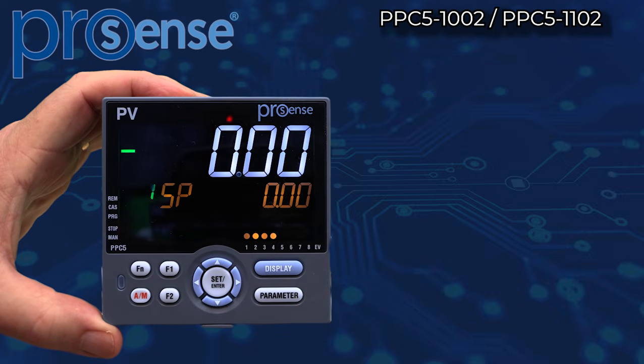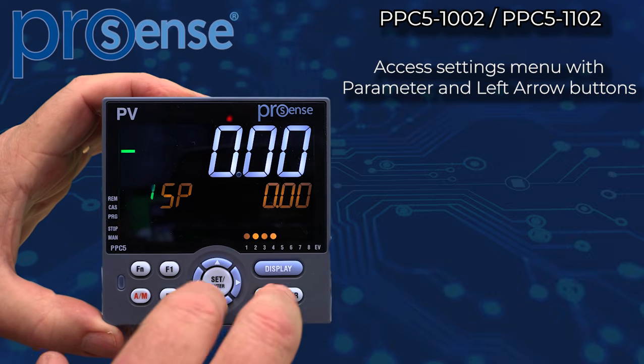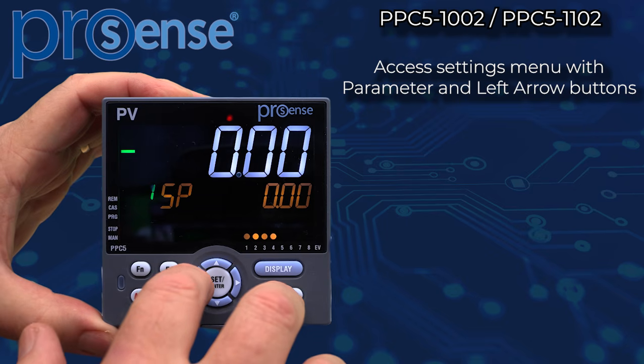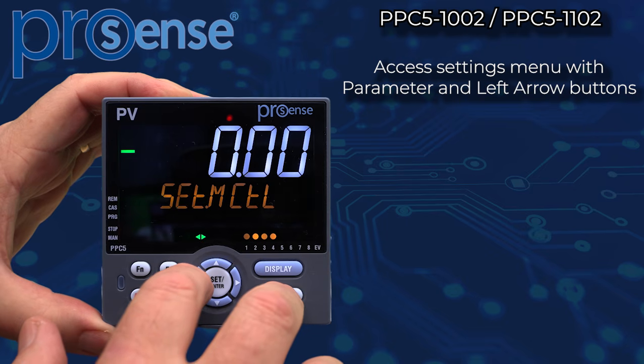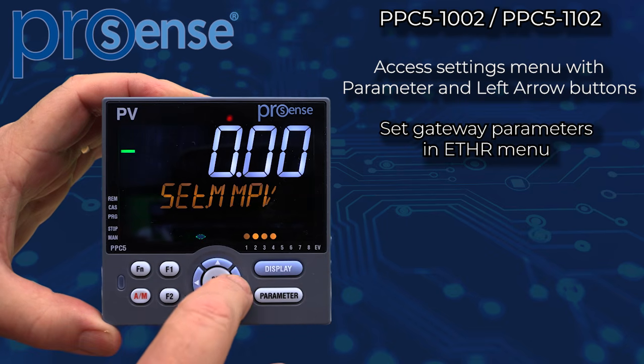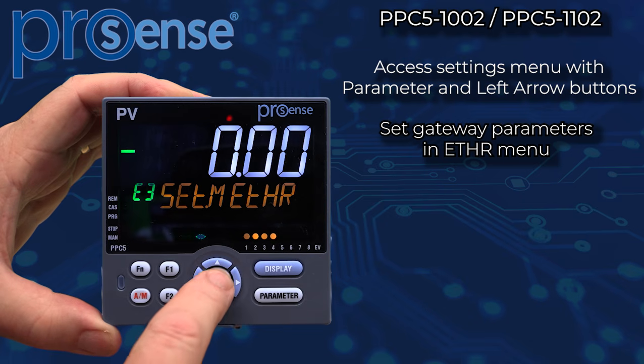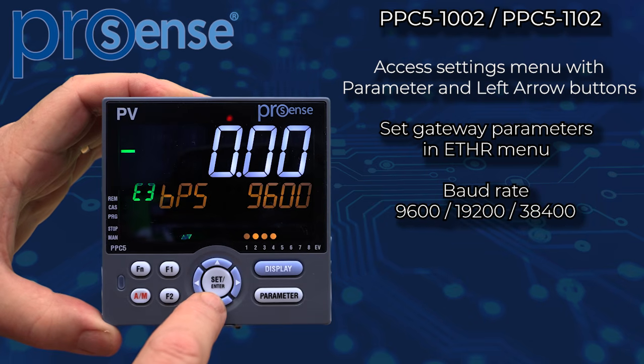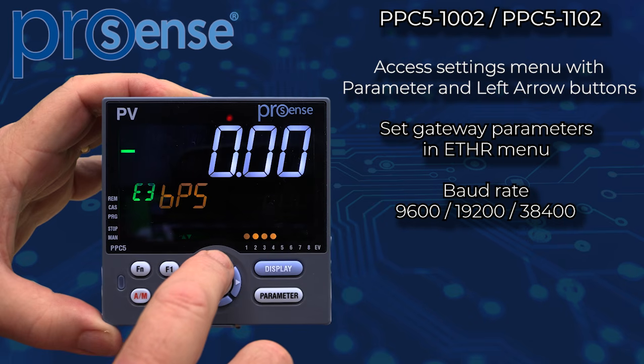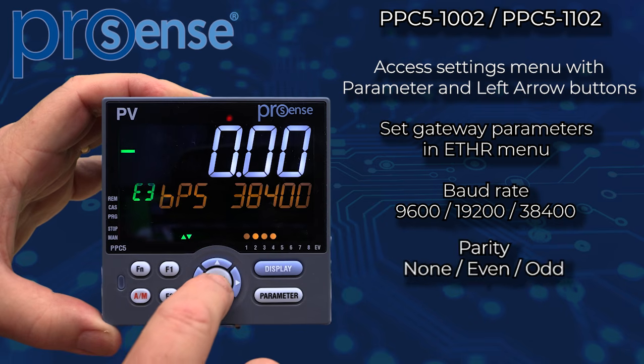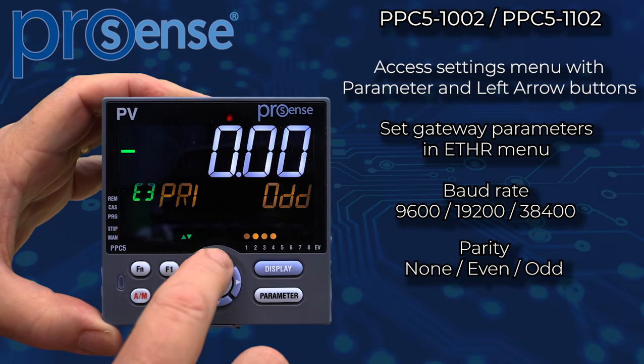Match communication settings on both sides. Access the settings menu by holding the parameter and left arrow buttons for 2 seconds. For the gateway controller, use the Ethernet settings group. Baud rate: 9600, 19.2, or 38.4. Parity: none, even, or odd.